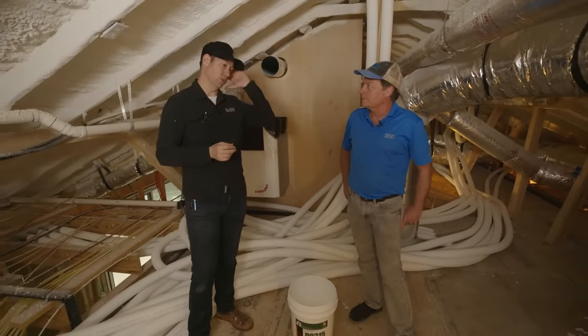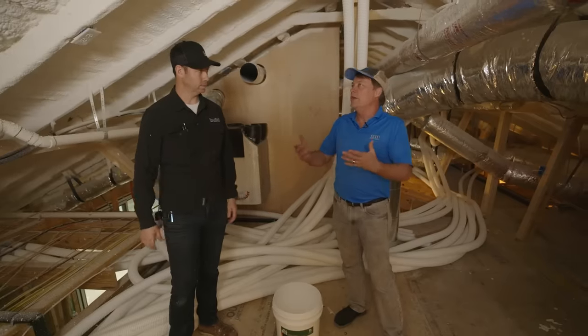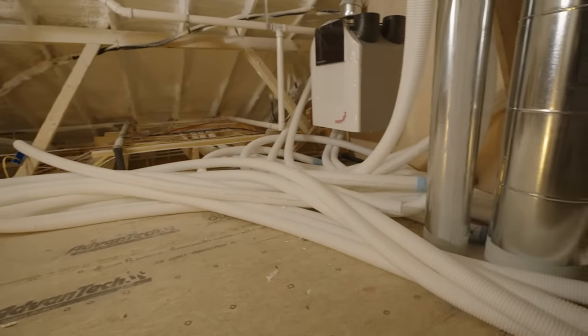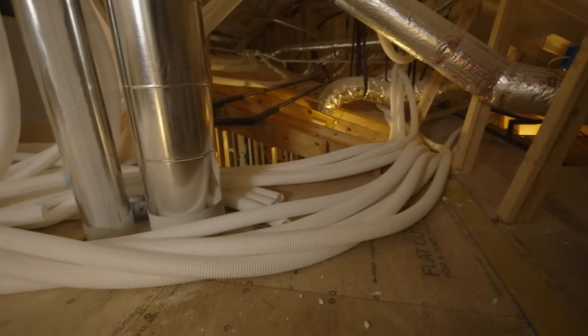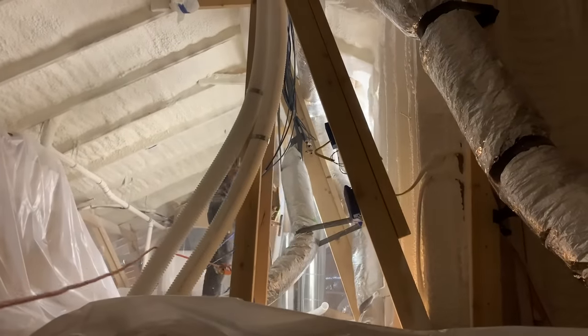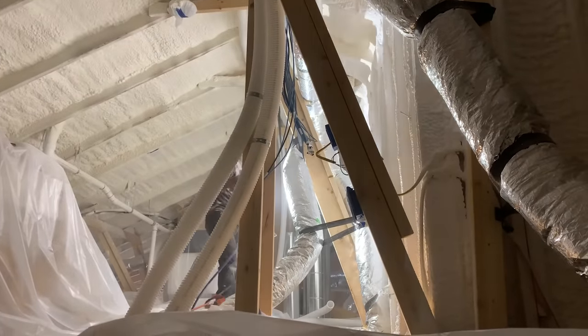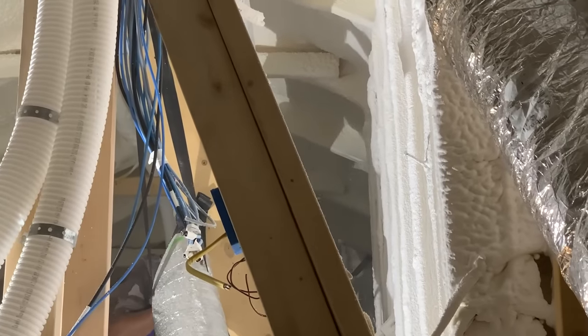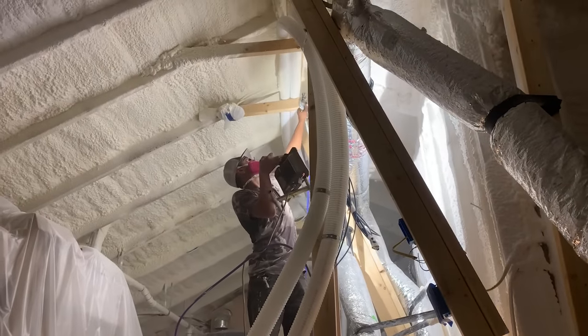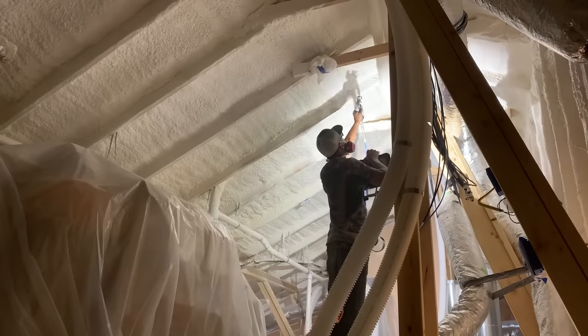What builders and homeowners need to know about spray foam in an accessible or storage attic is that foam is liquefied plastic, and cellular plastic can have fire go through it. There are two main types: thermoform and thermoset. Thermoform foams — your white, pink, or blue styrofoam types — will bend around 170–200 degrees and will propagate fire over 300 degrees, meaning they'll take fire from one location to another. Spray foams, on the other hand, are thermoset foams — they will not drip and rain fire; they'll only shrink and char.